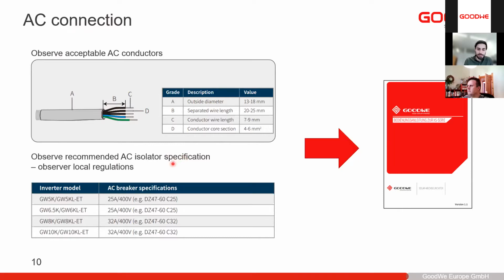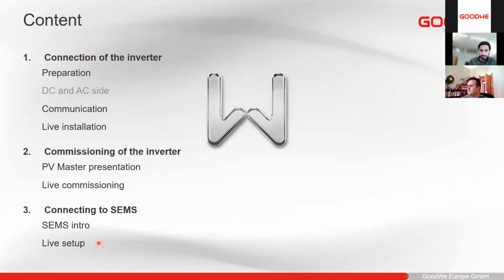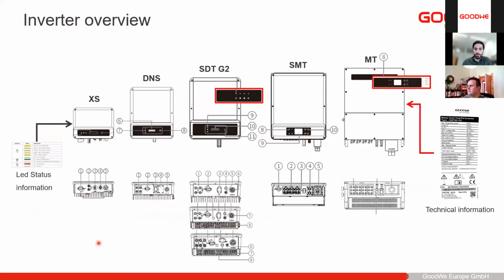It's also important to have some kind of breaker on the AC side, and the breakers are usually 1.25 times the rated output current. So make sure that you have the correct breaker for the inverter. You also see it here in the manual. So now we assume that you have installed the inverter, the DC and the AC side is connected, and now you need to install the communication.